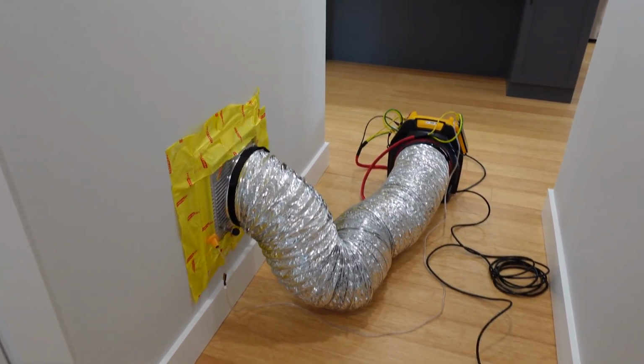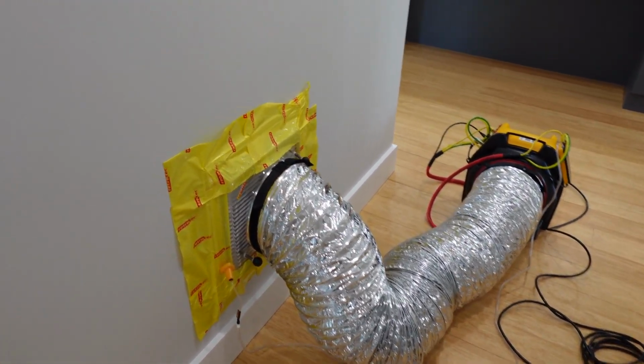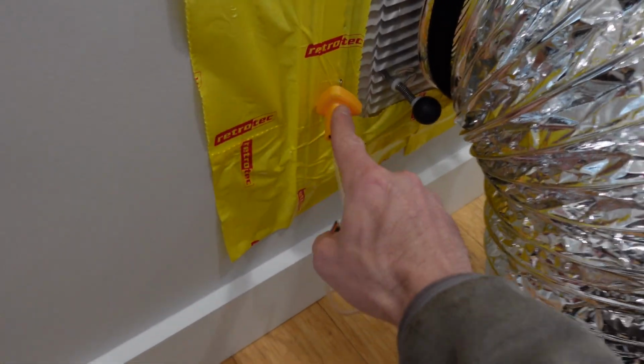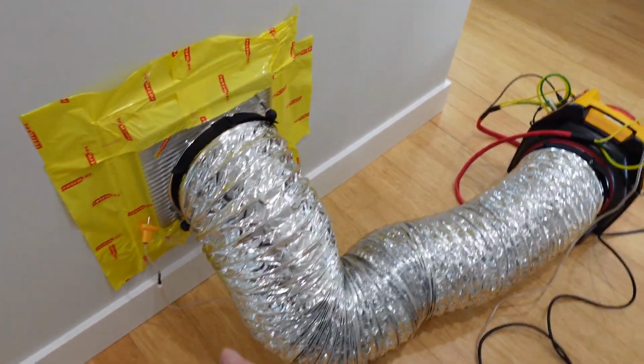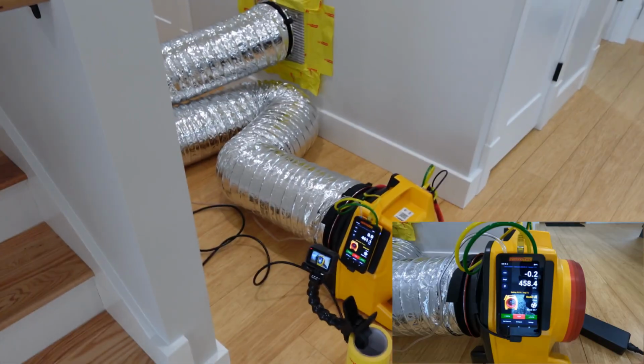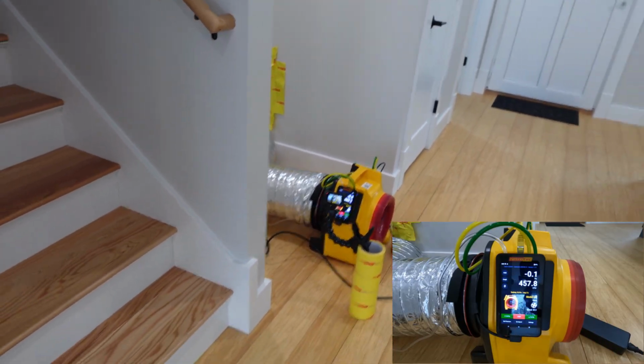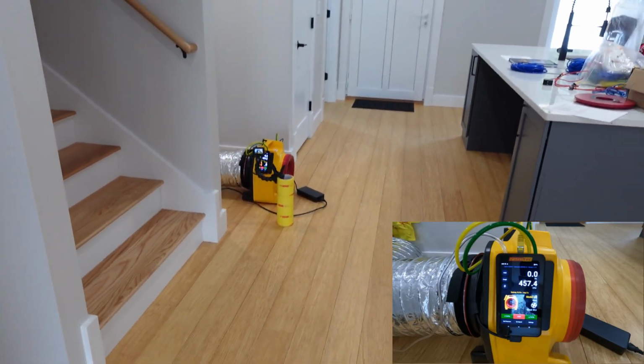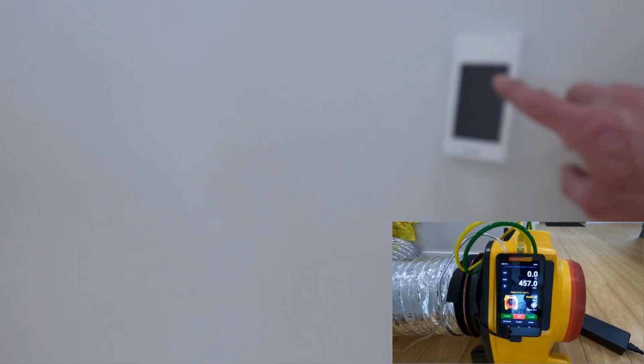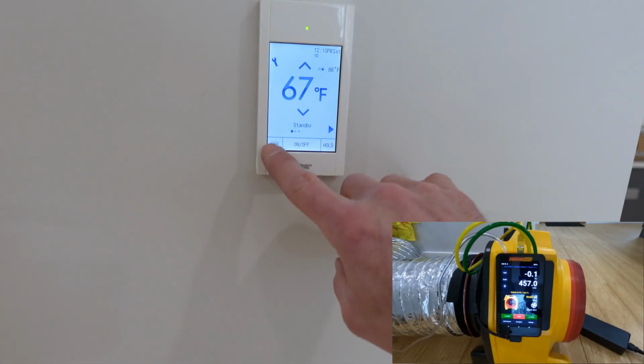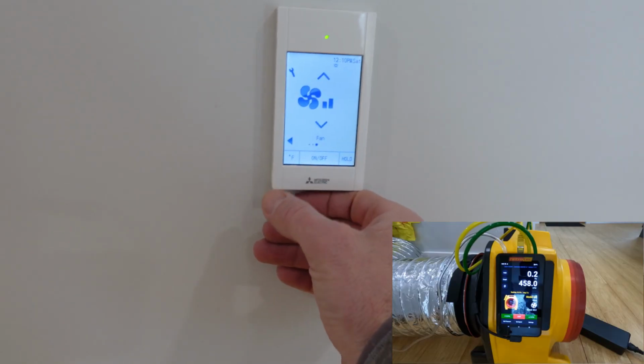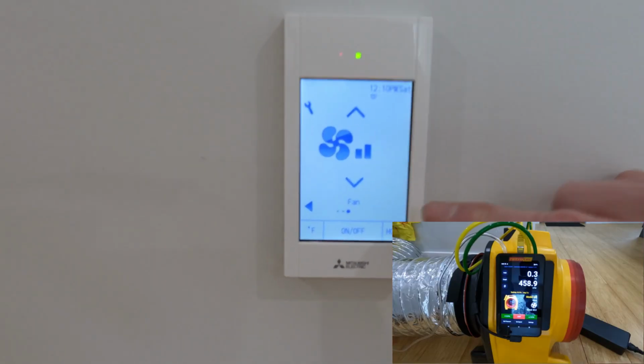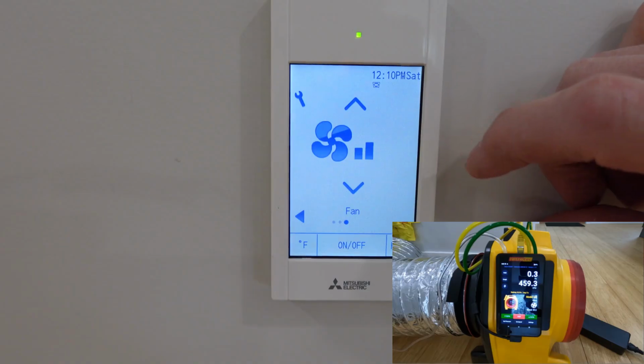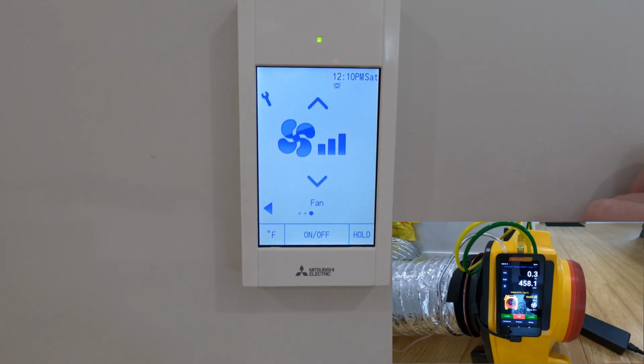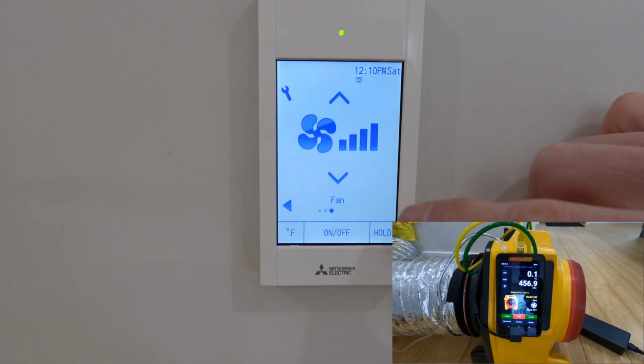All right, I got the test set up to run a total system airflow test. This probe here is going to measure the static pressure inside of the ductwork. All right, I set the pressure to 0 pascals, and it's reading 460 CFM, so that's pretty good. That's right around 400 CFM that I was searching for, and the fan speed is on low. 2 bars means low, 3 bars means medium, and 4 bars means high.